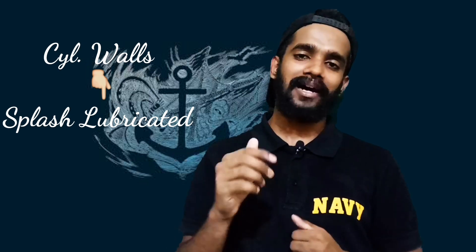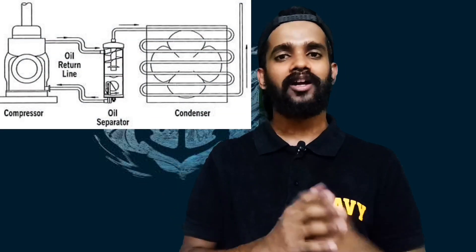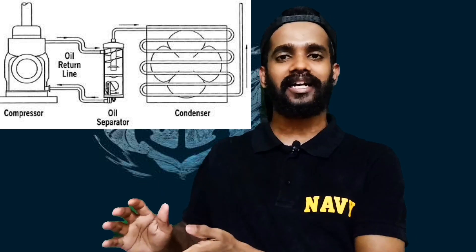The next question is: how does the oil actually get mixed with the refrigeration? The oil being referred to is the oil present in the compressor crankcase, which is used for lubricating purposes. The cylinder walls of the compressor in the marine refrigeration system are splash lubricated, and that's how some amount of oil is carried along with the refrigeration on the compressor discharge side. Oil separators are present at the discharge of the compressor so that they take away all the oil from the refrigeration and return the oil back to the compressor crankcase.